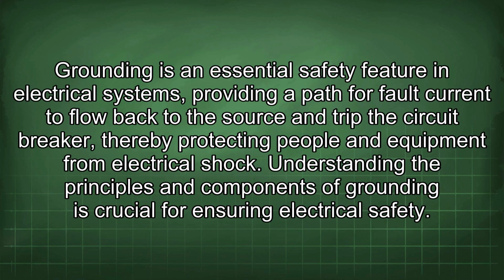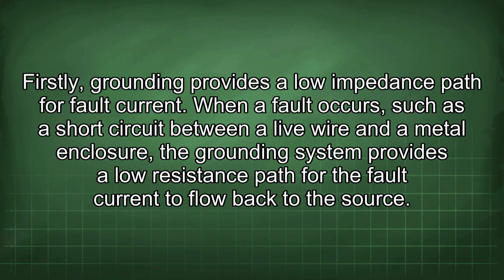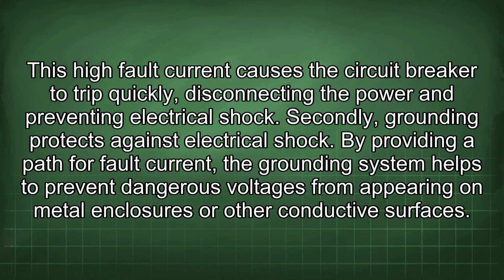Grounding is an essential safety feature in electrical systems, providing a path for fault current to flow back to the source and trip the circuit breaker, thereby protecting people and equipment from electrical shock. Understanding the principles and components of grounding is crucial for ensuring electrical safety. Firstly, grounding provides a low impedance path for fault current. When a fault occurs, such as a short circuit between a live wire and a metal enclosure, the grounding system provides a low resistance path for the fault current to flow back to the source. This high fault current causes the circuit breaker to trip quickly, disconnecting the power and preventing electrical shock.